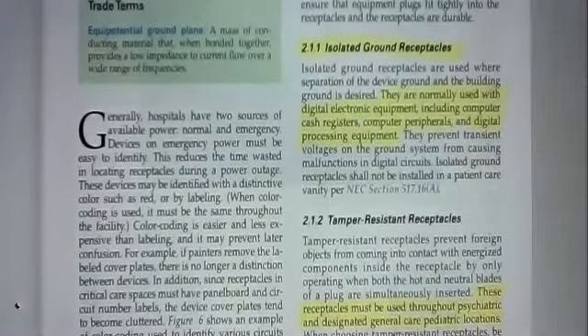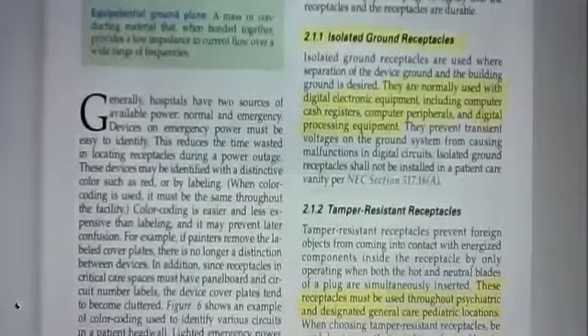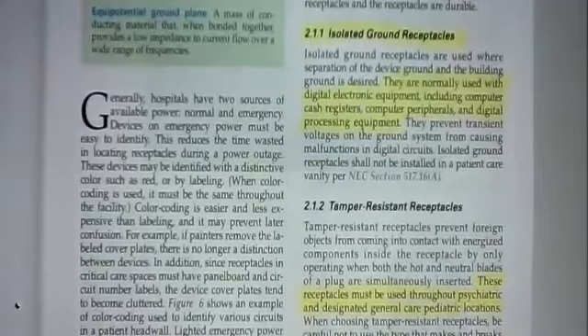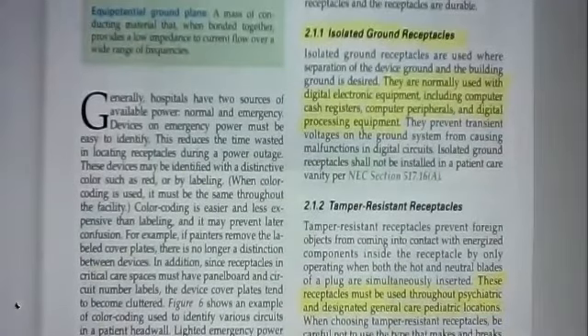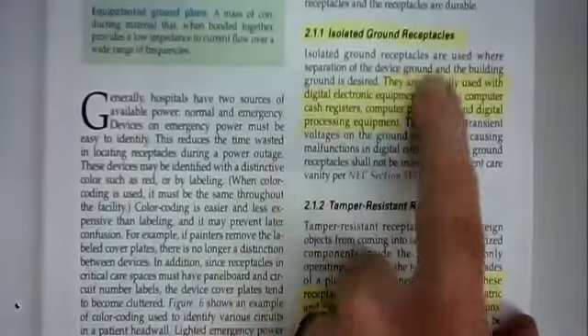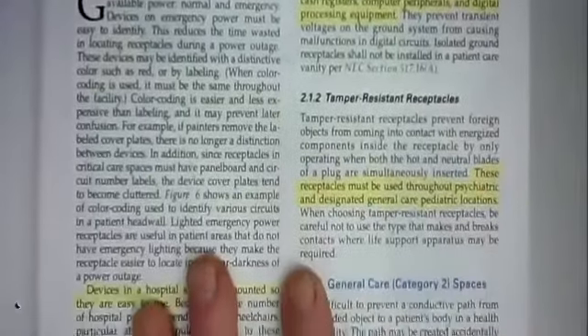So they came out with this idea of a clean ground, where you have a ground that goes from that receptacle all the way back to the panel, through the panel to the meter and out to the ground rod. They would not tie it to the grounding system of the electrical bond for the metal parts. They'd take it out to the ground rod, and that way you had a clean ground and no interference would be felt on that receptacle from other receptacles. So that's what they mean by an isolated grounding receptacle.